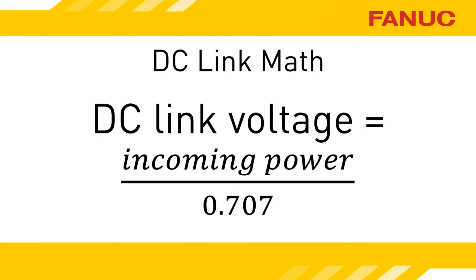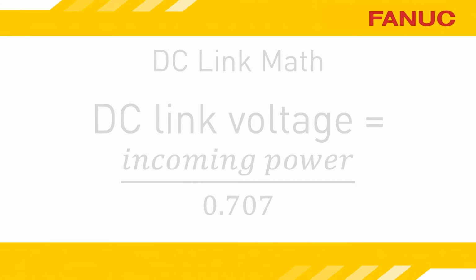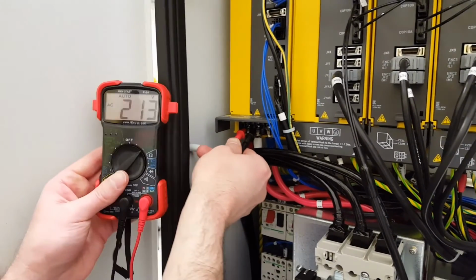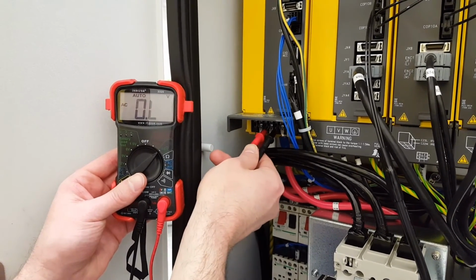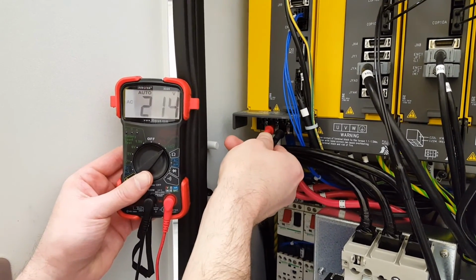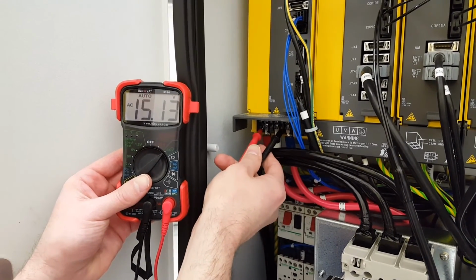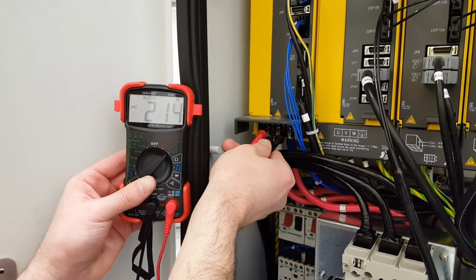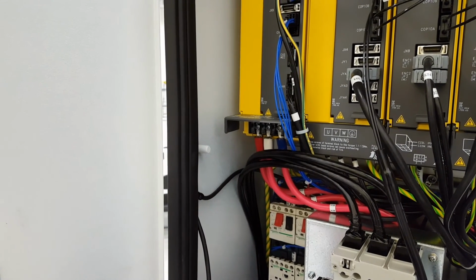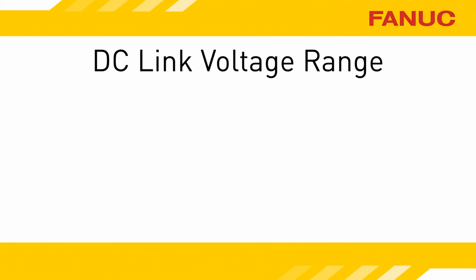As promised, math. Don't worry, it's easy. To calculate the DC link voltage, take the value of the incoming AC and divide it by 0.707. The AC used for the DC link enters the power supply at the bottom. You determine the incoming AC value by checking it phase to phase. We have no interest in phase to ground for this. The DC link voltage depends on whether your system is using 200 volt or 400 volt amplifiers. Check the label at the top of the power supply module if you are unsure.